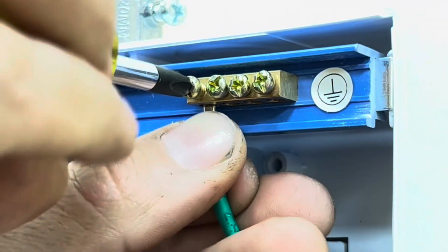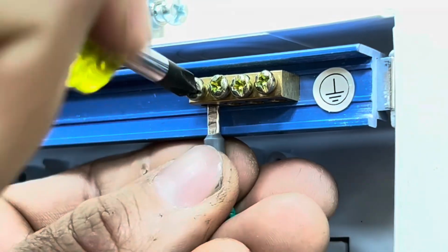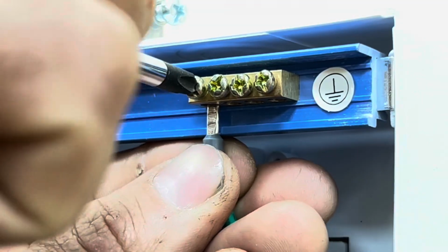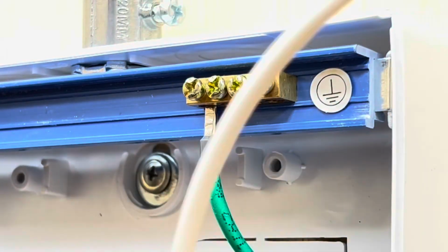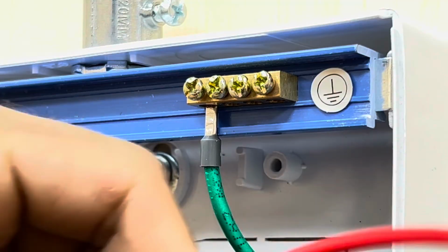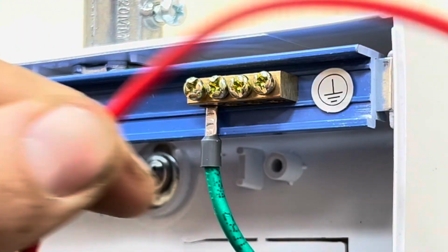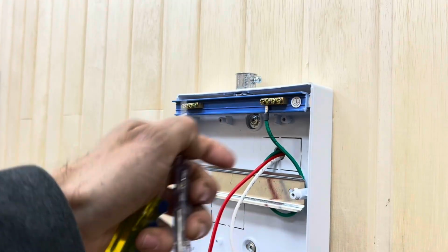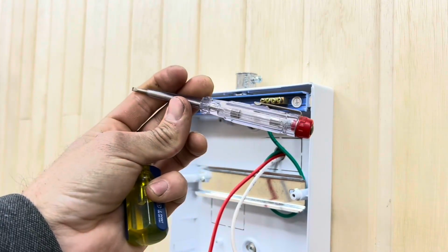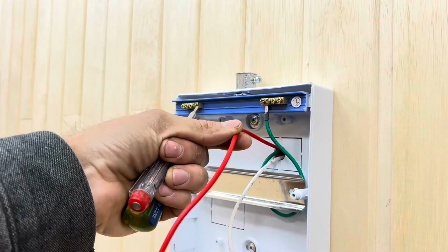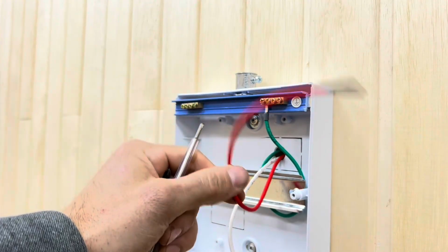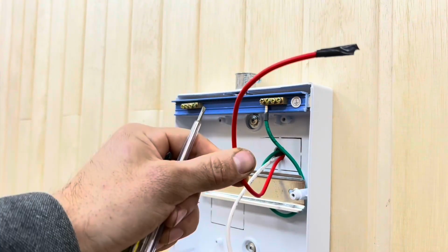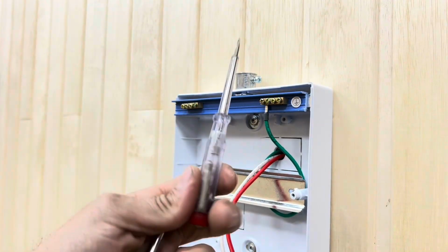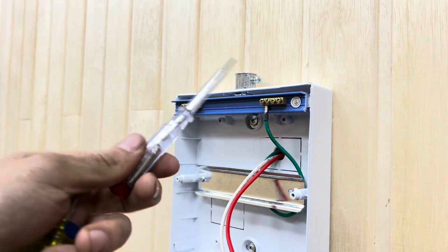Our ground wire, which comes from the main panel, is always the green wire, at least here in Chile. The white is neutral and the red is the live wire, meaning this is the one that carries the electricity. In any case, I recommend that you always check with a multimeter or a voltage tester which of the wires is the live one, since not everyone respects the color codes when doing electrical installations. So the sure way to know is with a voltage tester or a multimeter.